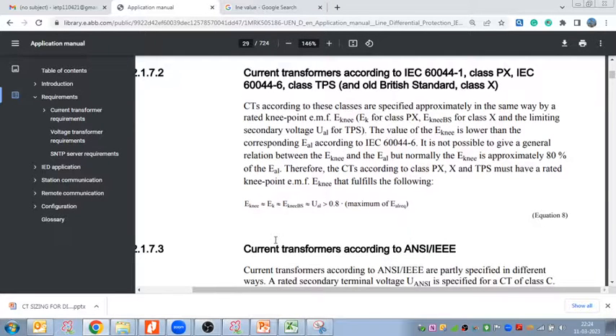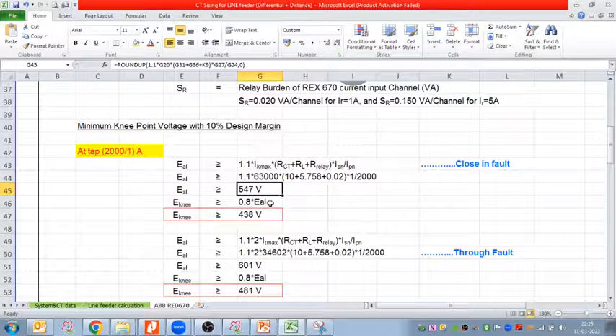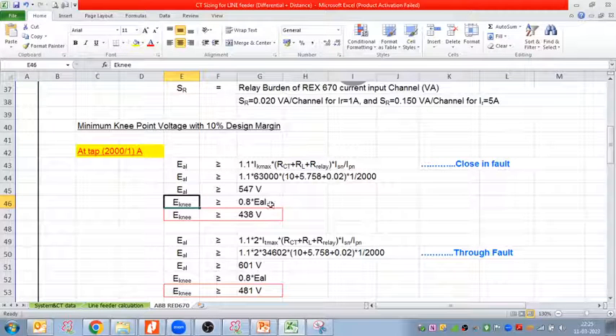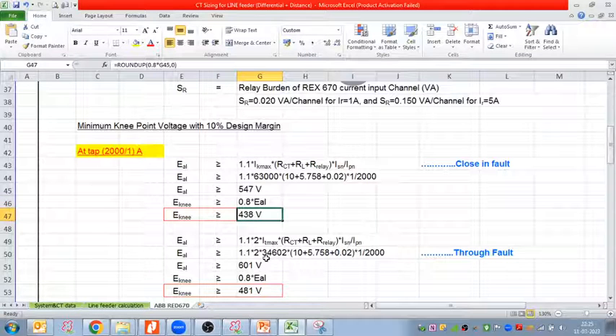They are telling that the CT knee, E knee, should be equal to EK, and that equals E knee BS in British standards, which shall be greater than 0.8 into maximum EAL required. So due to equation 8, I took this equation and put here 0.8 into EAL required. E knee should be higher than 80 percent of this only. So E knee should be higher than 438 voltage. That is, the CT minimum knee point voltage should be higher than 438 voltage.